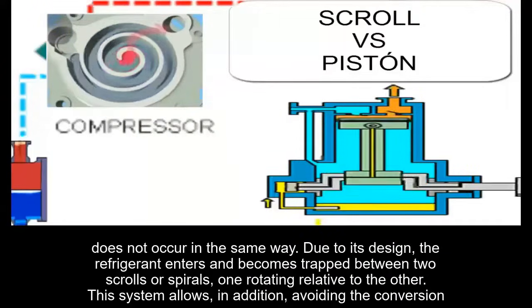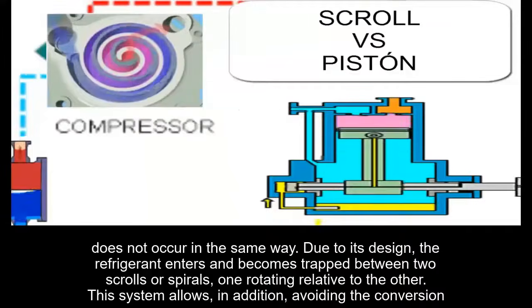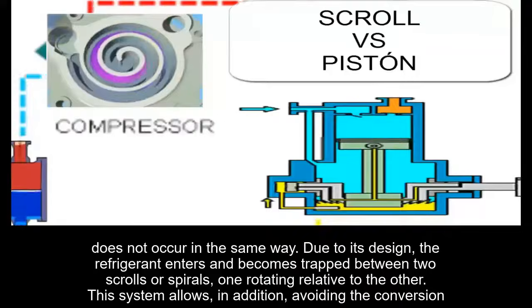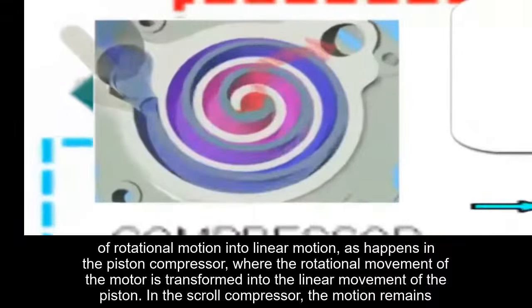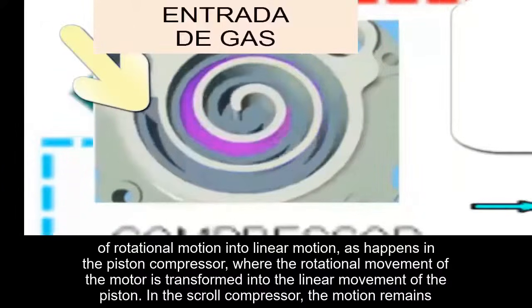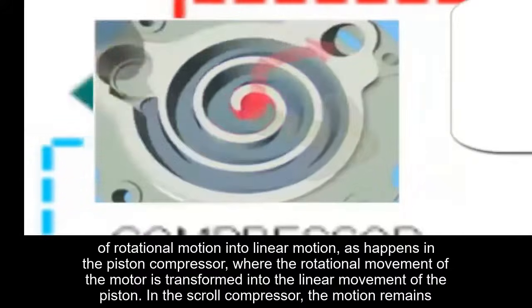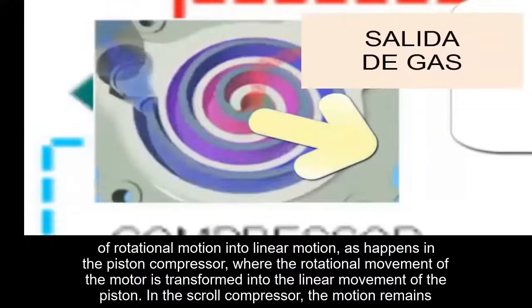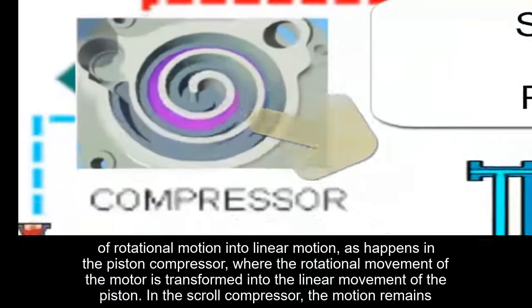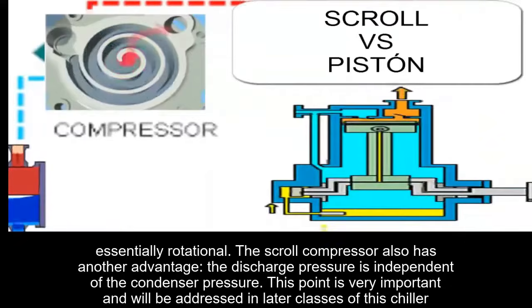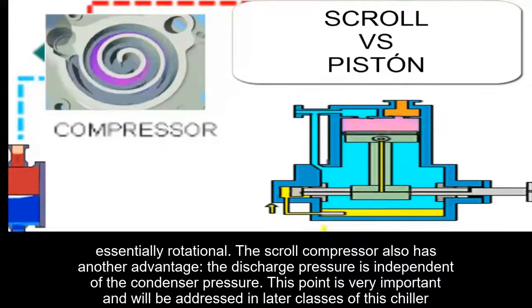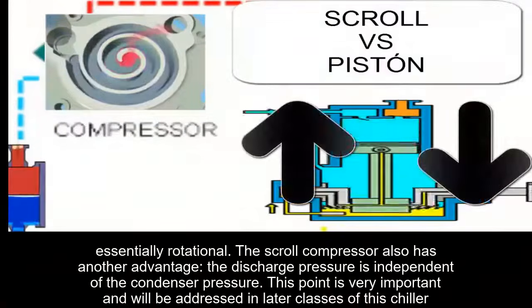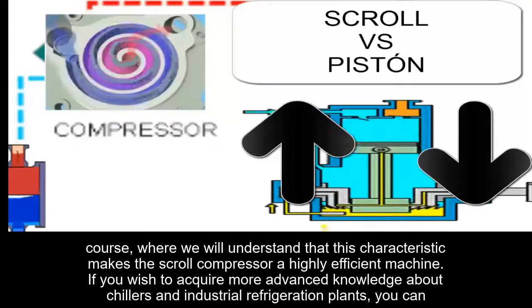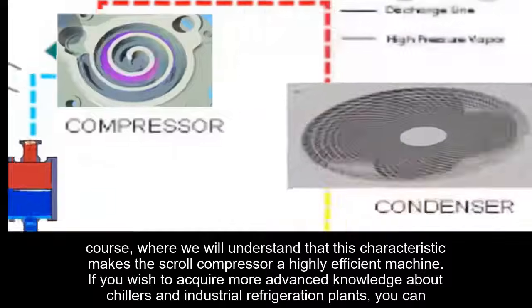Due to its design, the refrigerant enters and becomes trapped between two scrolls or spirals, one rotating relative to the other. This system allows, in addition, avoiding the conversion of rotational motion into linear motion, as happens in the piston compressor, where the rotational movement of the motor is transformed into the linear movement of the piston. In the scroll compressor, the motion remains essentially rotational. The scroll compressor also has another advantage. The discharge pressure is independent of the condenser pressure. This point is very important and will be addressed in later classes of this chiller course, where we will understand that this characteristic makes the scroll compressor a highly efficient machine.